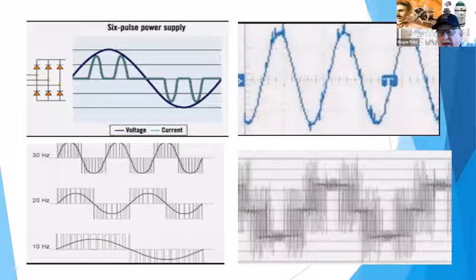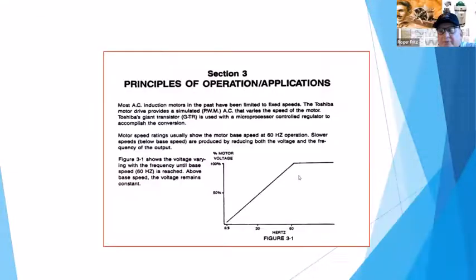This is more of an idea of what the output pulses actually look like. It's important to understand that the motors are actually capable of handling the higher peaking voltages. Some of the earlier installations and motors were, let's say, 1,000 to 1,200 volts peaking. Well, they were seeing maybe 750 volts with a straight sine wave maximum peak. And with some of the PWM that's out there, they were seeing peaks all the way up to 12, 13, 1400. And what happened, it would do damage to the motor.